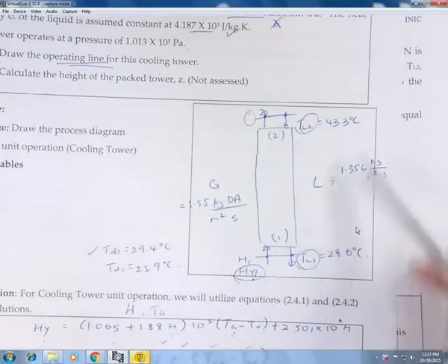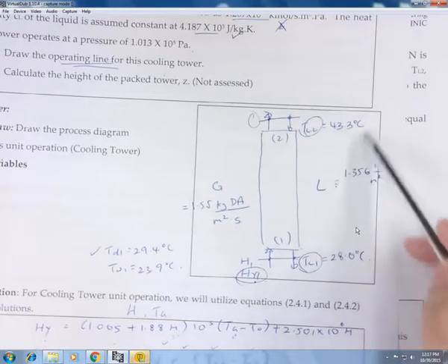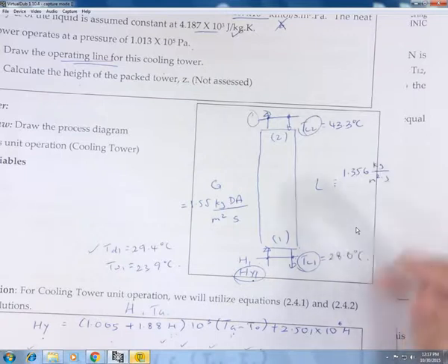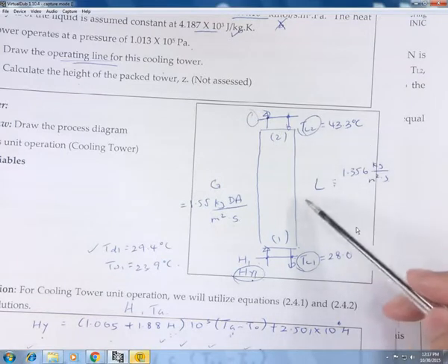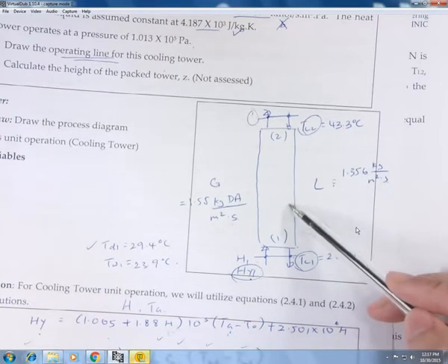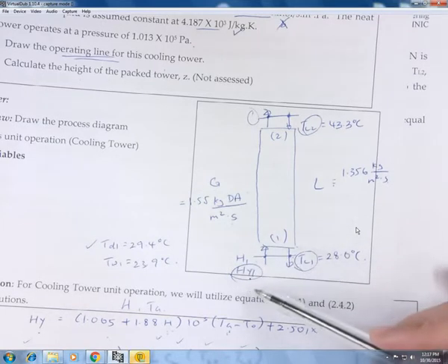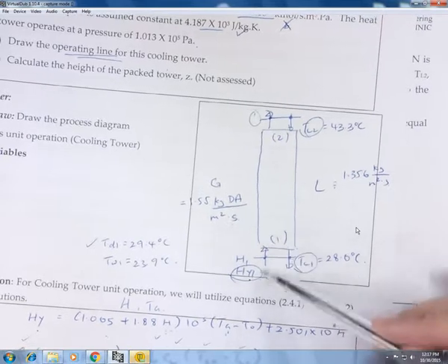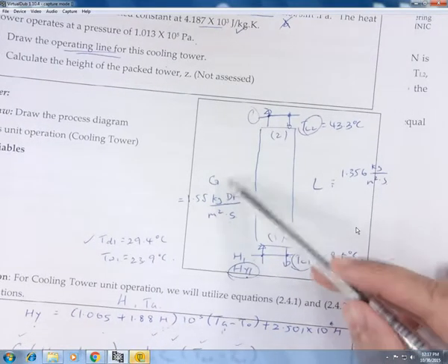Sometimes they produce more and sometimes they produce less. Sometimes the temperature comes in higher, sometimes the temperature comes in lower. But remember, for this particular cooling tower unit, you cannot tell them to change because their process needs it. They will send to you whatever they have to. So if you are in charge of this unit, the only thing we can manage is the air side. In real, the only thing we can change is the air flow rate because we can't really change the air humidity. That one is fixed by our environment. So the only action that we can actually do is the air flow rate.